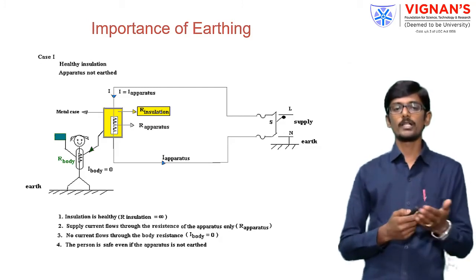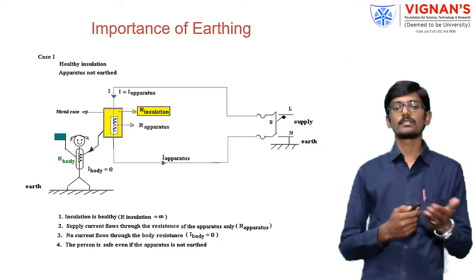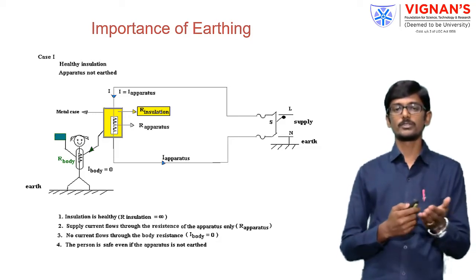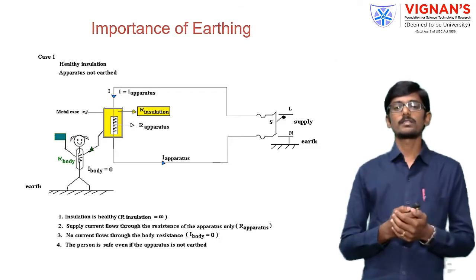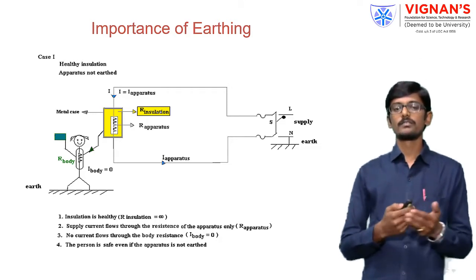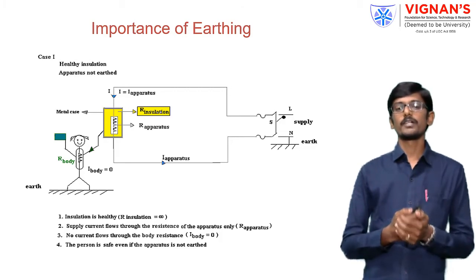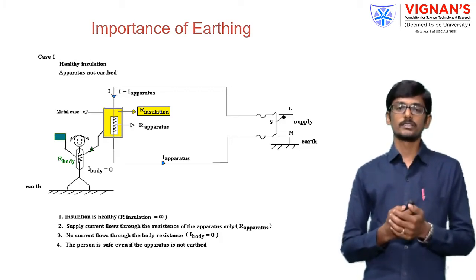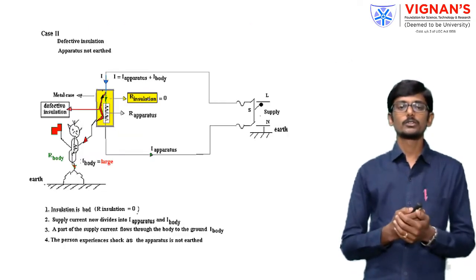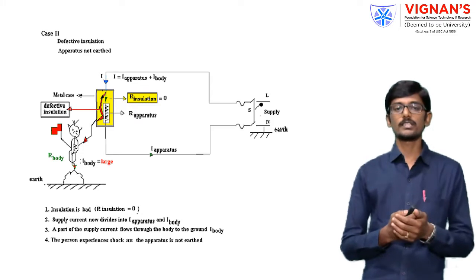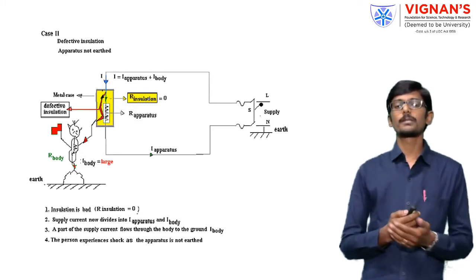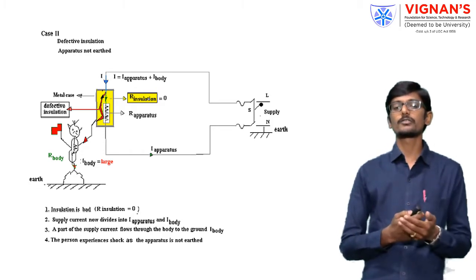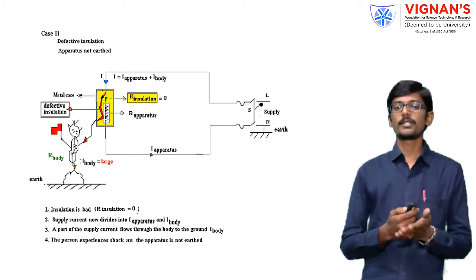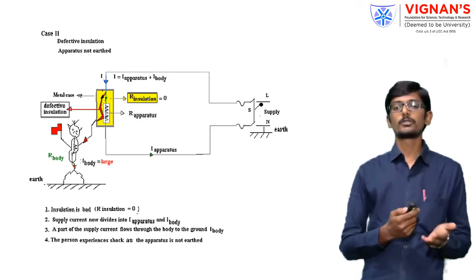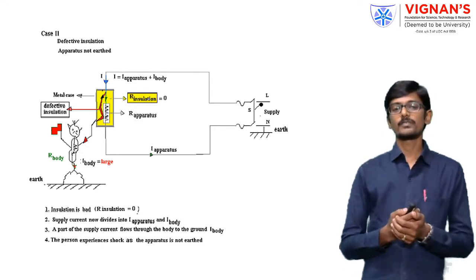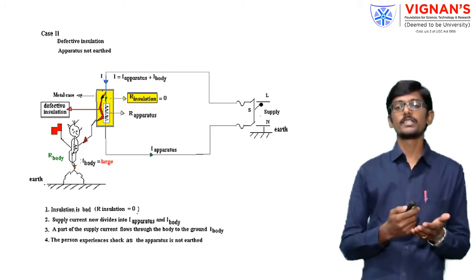There is no current flowing through the body of the person who is operating that equipment or some load or any device which may be used. So in this case, the person operating this device will be protected safely when the insulation is in healthy condition. Case 2 shows defective insulation and the apparatus is not earthed. So when the person is operating with defective insulation and there is no earthing protection, then the supply flows from the input through the device and also through the person operating that device, and he may experience some electrical shocks.